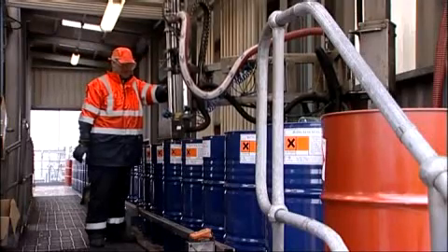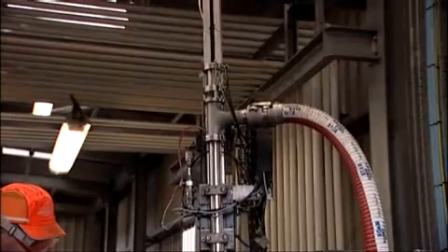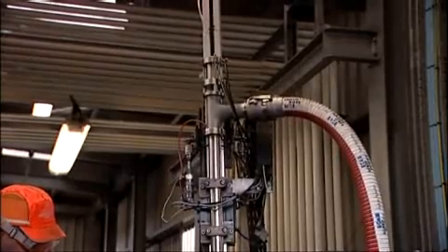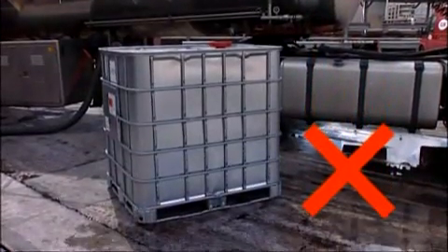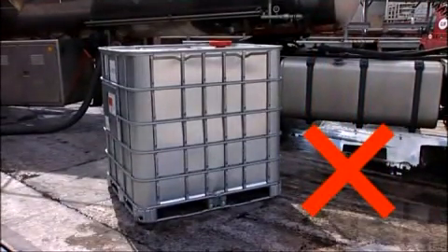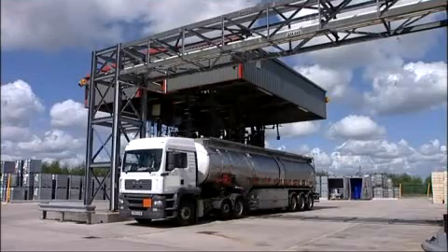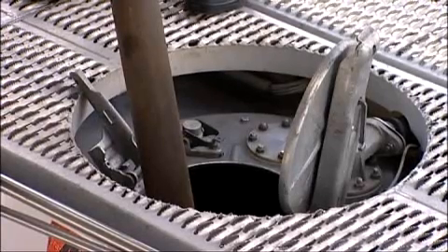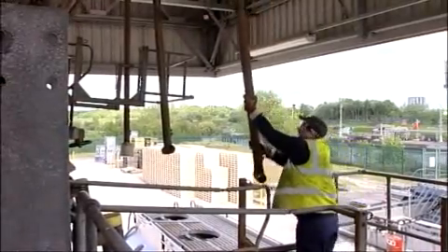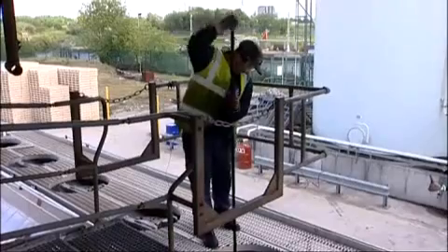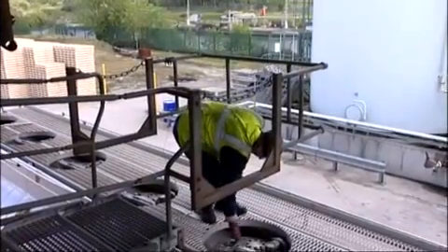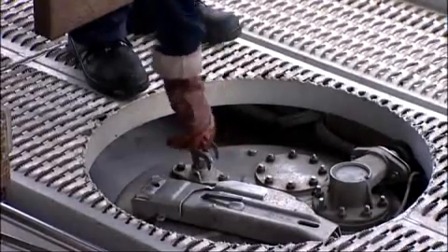It is particularly important that the velocity of the incoming liquid or liquid being discharged is controlled, so operations such as gravity filling of IBCs from road vehicles should be avoided. Once a filling operation has been completed or a vessel has been mixed, it may be necessary to dip or sample, and a sufficient time should be allowed for the accumulated electrostatic charge to dissipate. The charge relaxation time.